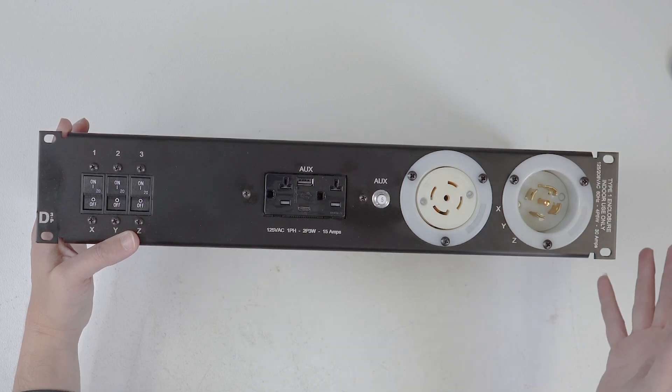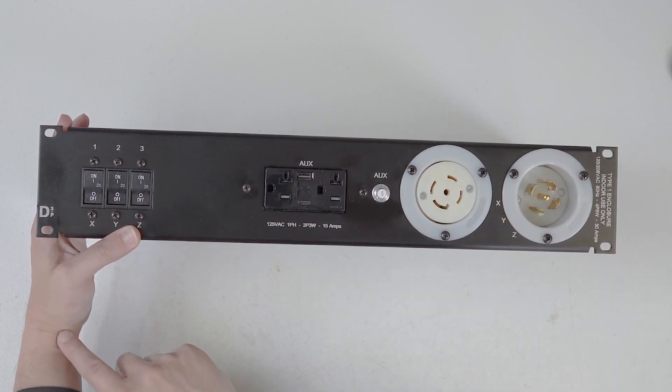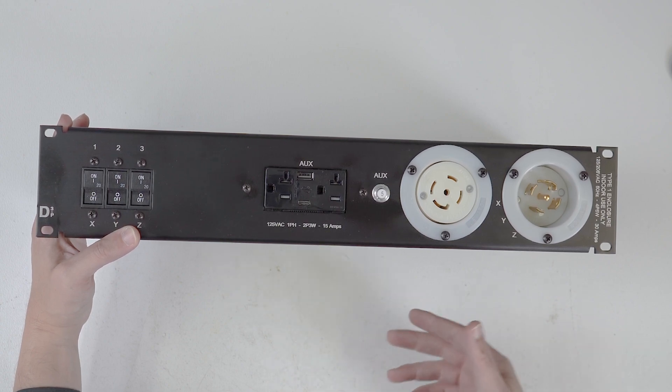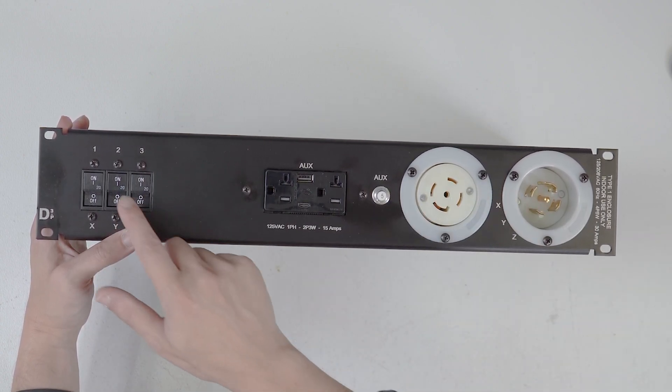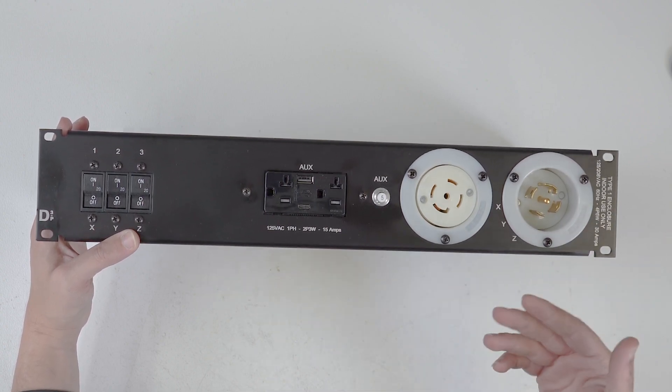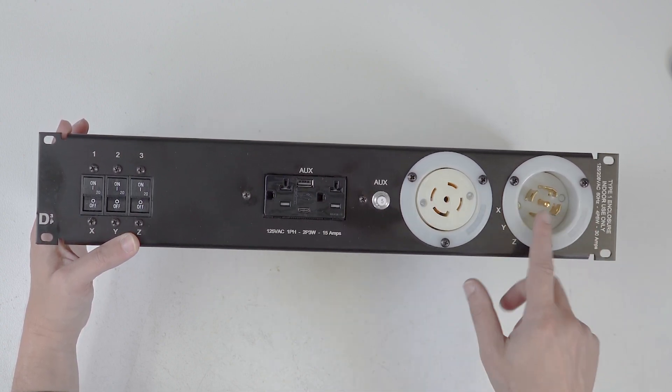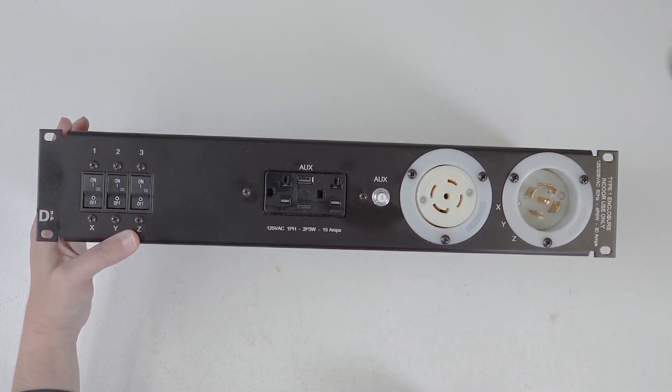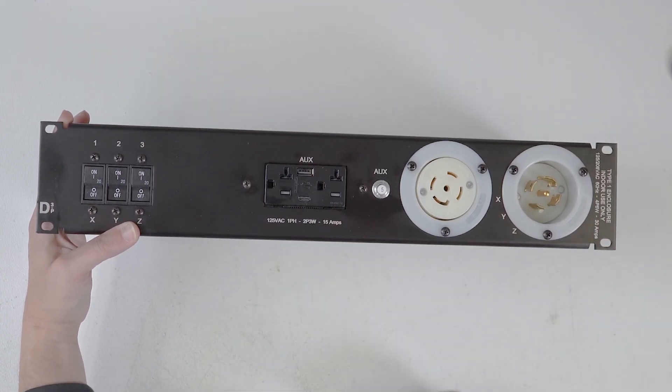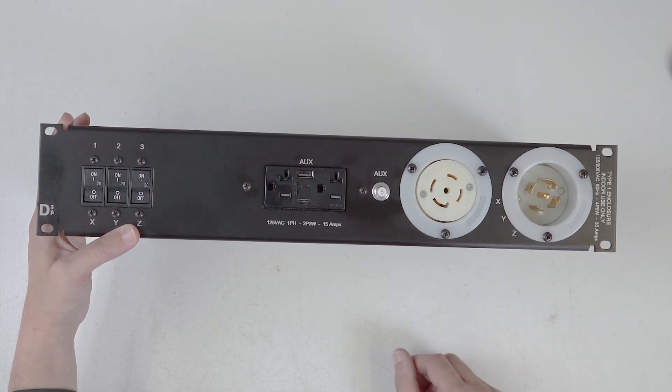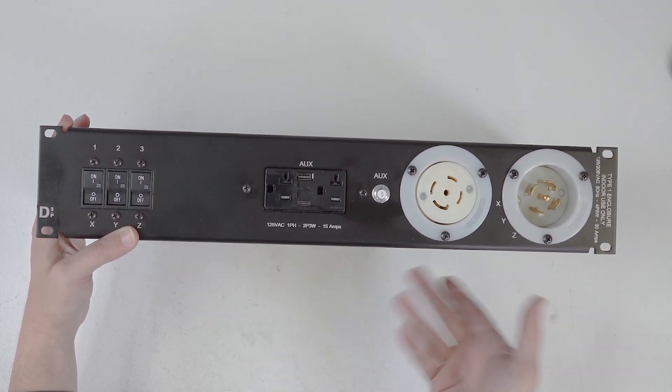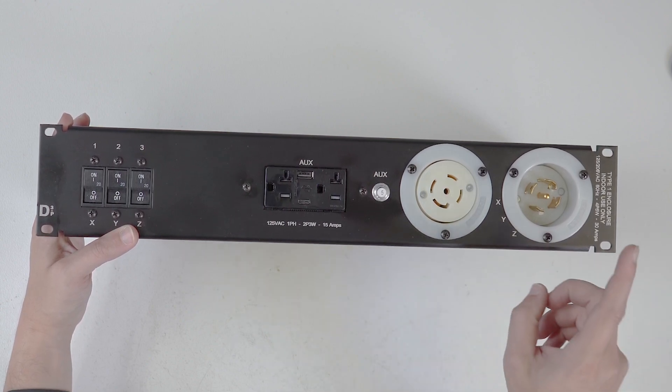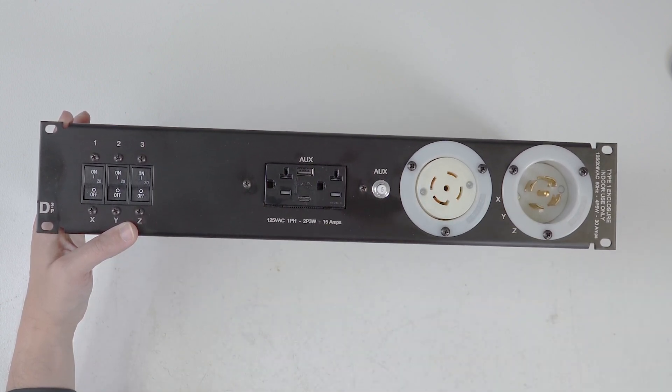Because of that, we do have breakers that are 20 amp because, as you know, a Power Con connector is only rated for 20 amps. So, it does step this down to 20 amps if needed. I shouldn't say step down, but it won't let you exceed a 20 amp load even though 30 amps are available to you here. Now, that being said, everything we have here at LM is built per order from the cases down to the distro. So, if you do want a 20 amp inlet, we can do that for you because they are the same size.